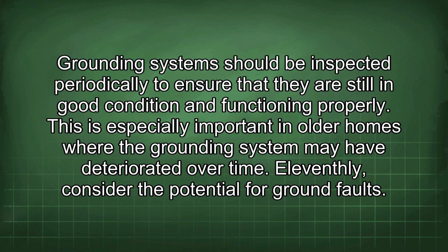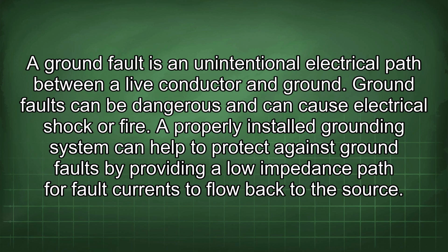11thly, consider the potential for ground faults. A ground fault is an unintentional electrical path between a live conductor and ground. Ground faults can be dangerous and can cause electrical shock or fire. A properly installed grounding system can help to protect against ground faults by providing a low impedance path for fault currents to flow back to the source.